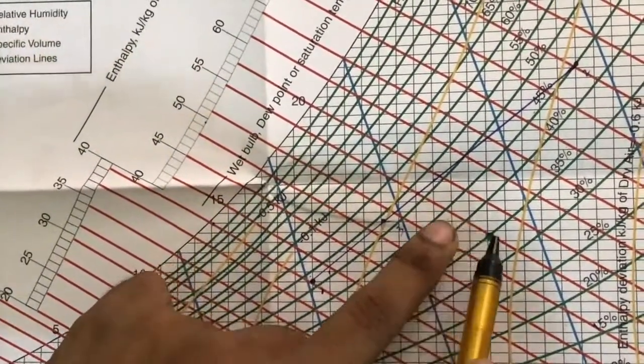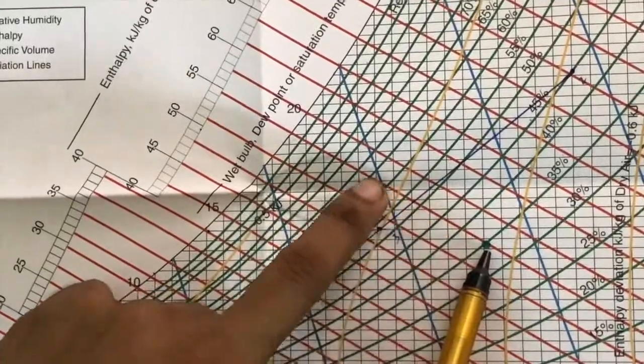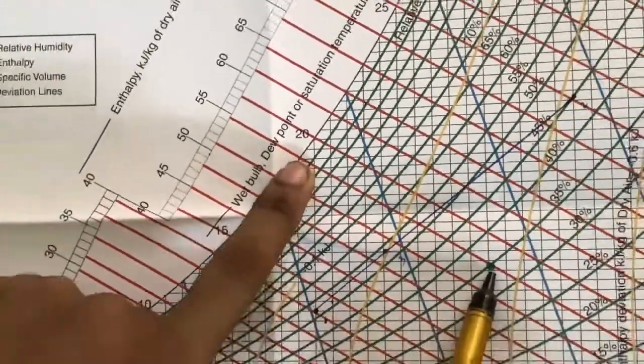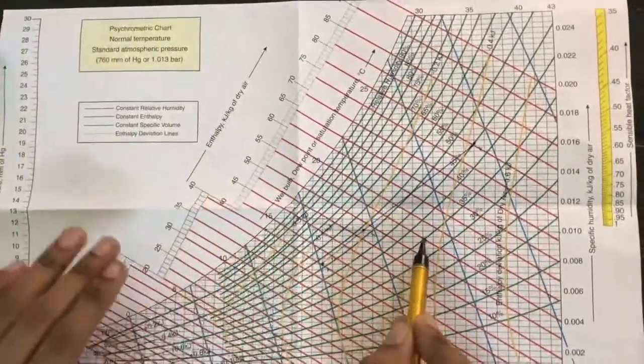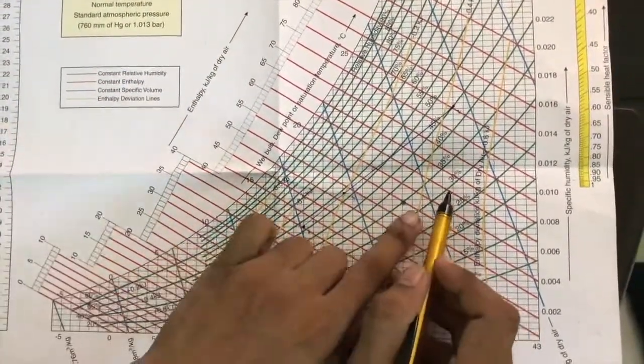It is about 19 degrees. So from this scale itself we get the wet bulb temperature. For dew point temperature draw horizontal line, for wet bulb temperature draw inclined line which is parallel to the enthalpy line.